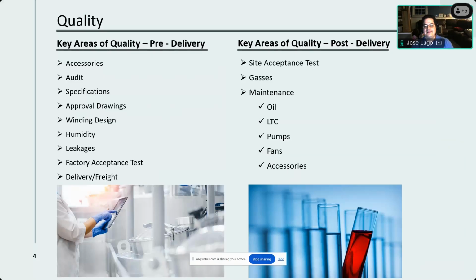The key areas of this quality post-delivery. So there's pre-delivery and then there's post-delivery. For the delivery, you want to make sure that it arrives safely and is tested positively. Post-delivery, the thing is there, and you take responsibility for it at this point. You paid off the transformer manufacturer everything that you need to. You do a site acceptance test, which means that you test it to make sure that nothing happened during delivery. You test the gases to make sure that it matches what they did in the factory acceptance test. There's no reason why the gases should increase at that point because you're not energizing it whatsoever.